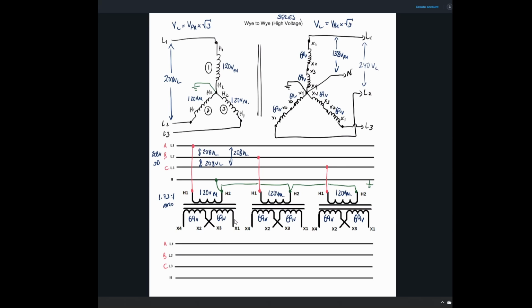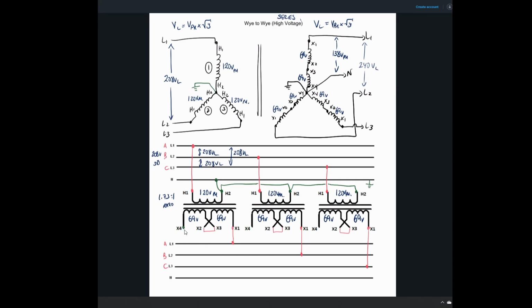So we've got 2 and 3 that are jumpered together to create that series connection. Line 1 is going to be fed from X1 of the first transformer. Line 2 is going to be fed from X1 of the second transformer. And line 3 is going to be fed from X1 of the third transformer. And then we need our neutrals tied together. So all of our 4s are going to tie together, and they're going to feed that neutral bus there. That neutral bus is also bonded to ground, and we need to grab all of these guys and put them at the same potential.